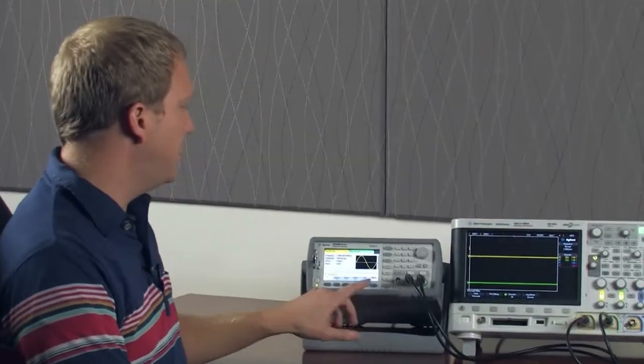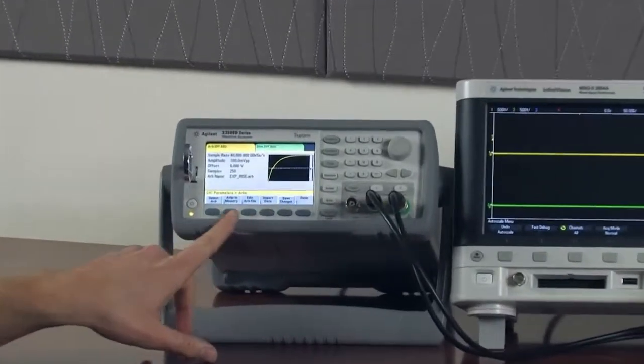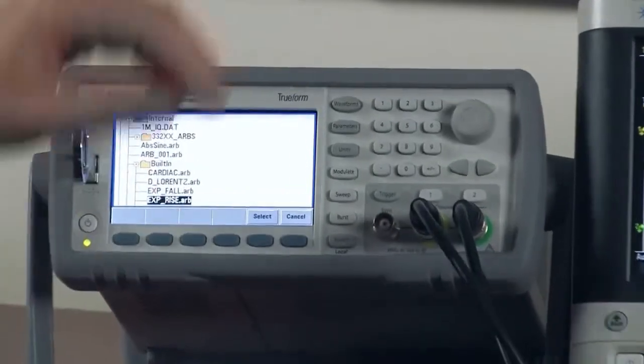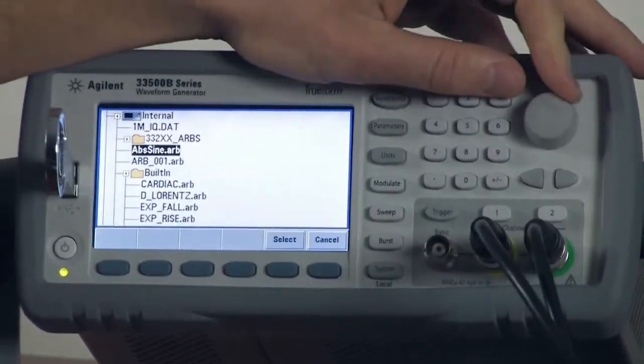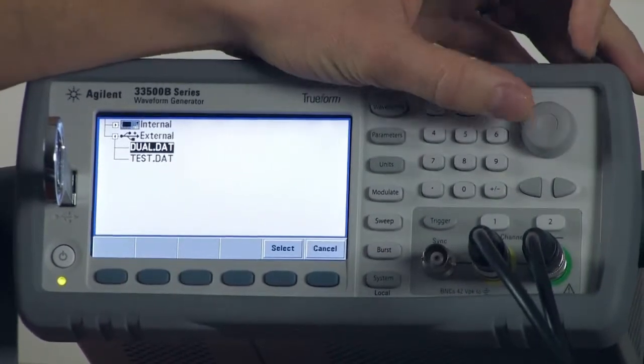Now if you go to the instrument and you go to ARB, ARBS, select ARB, and you want to go up to external because I saved it here on a thumb drive. I have a file called dual .dat.